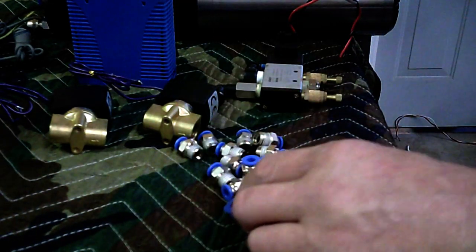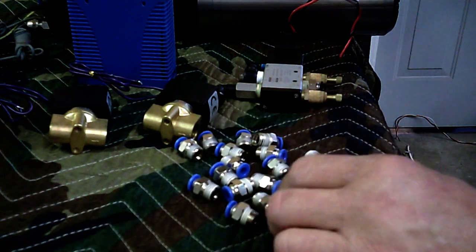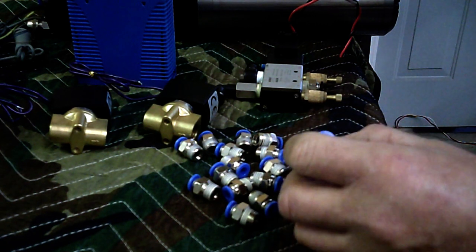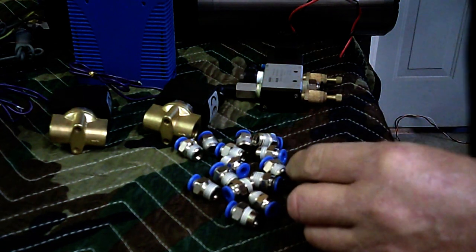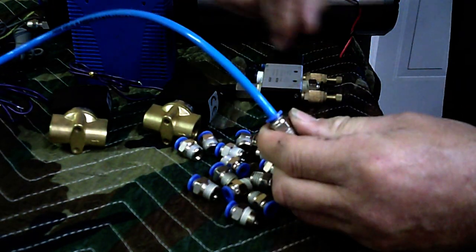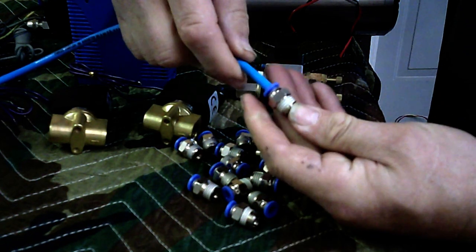And these are some quarter NPT by six millimeter—well that's just a cap—quarter NPT by six millimeter connectors, press fit connectors. I kind of like these because all you have to do is push the tube in, six millimeter tube obviously, and pull back and it's locked in place. If you ever need to remove it, you push in, hold that back, pull it out.